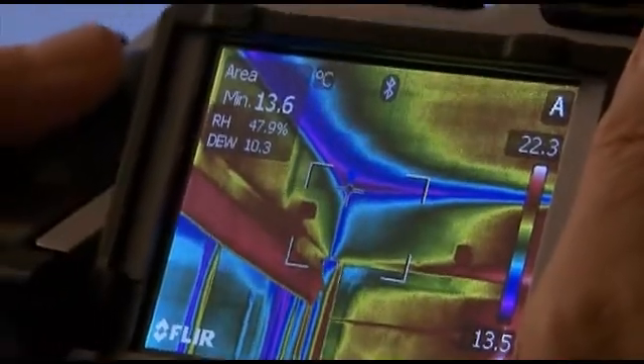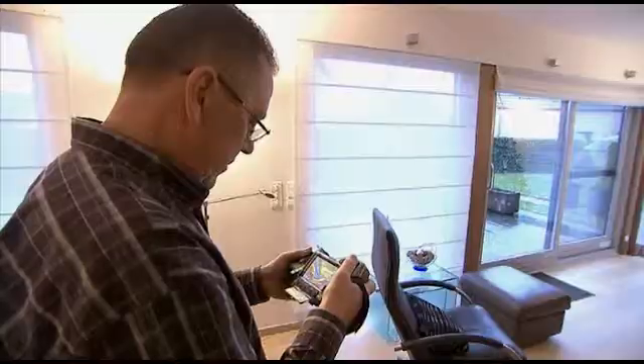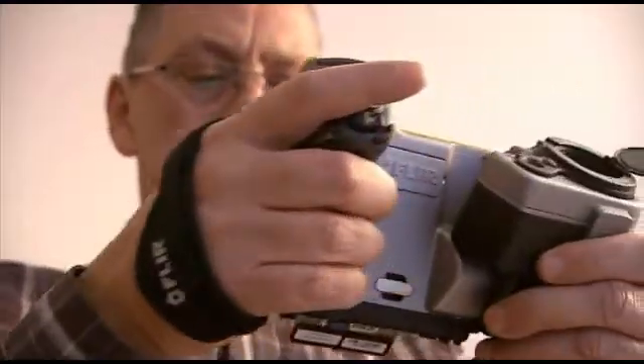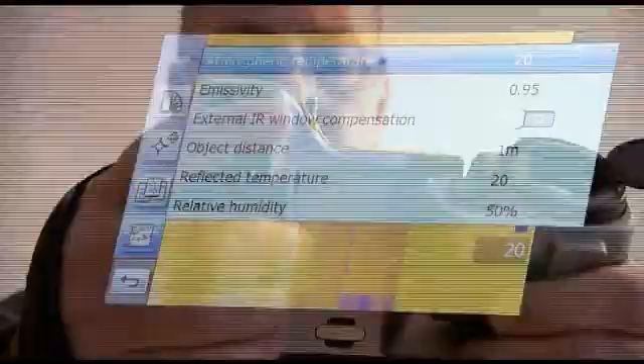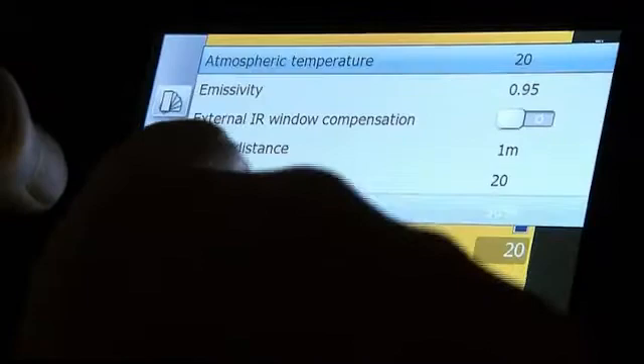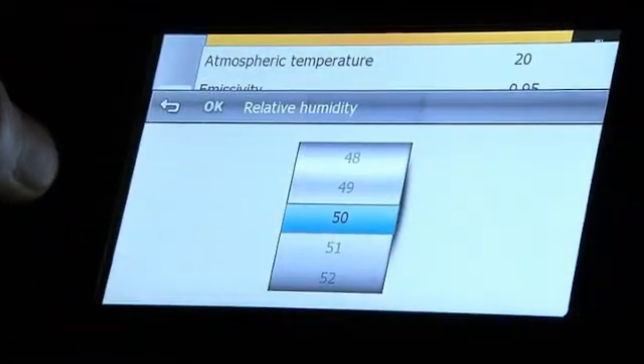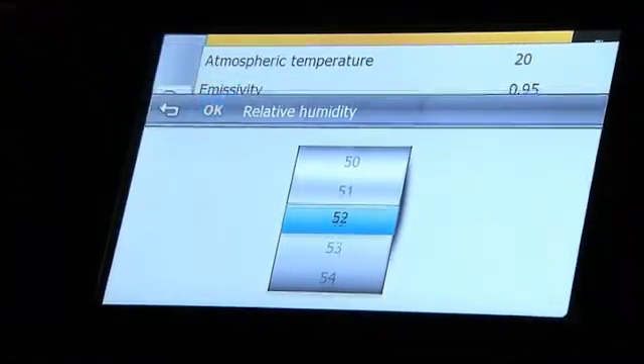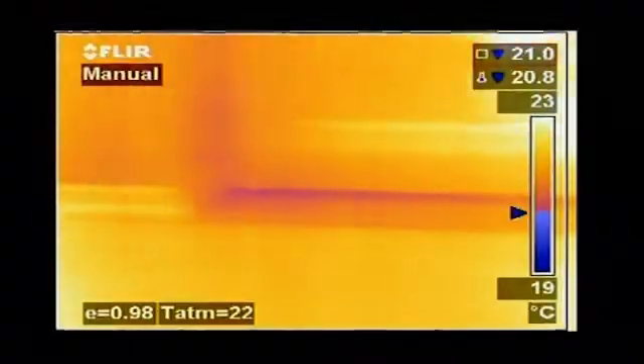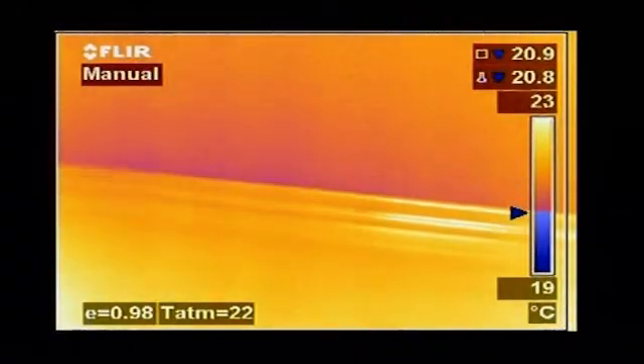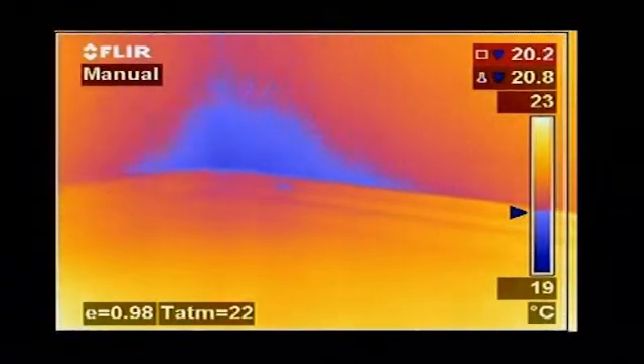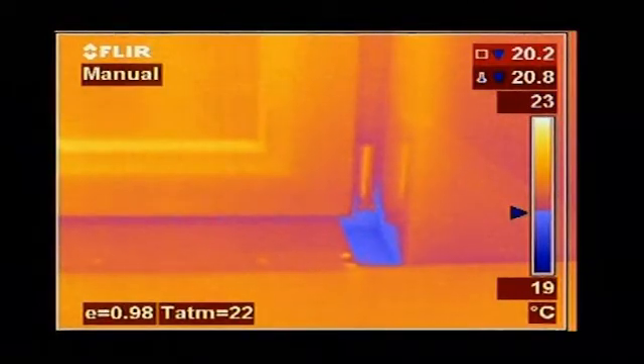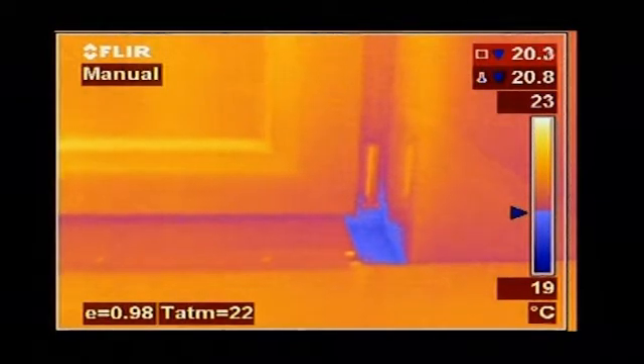If you don't have an Extech moisture meter to hand, all parameters used to identify potential condensation areas — such as relative humidity and temperature — can be set in the camera. The FLIR thermal imaging camera will calculate the dew point. Thermal imaging cameras with dew point visualisation software can highlight endangered locations automatically and provide a colour alarm in the image.